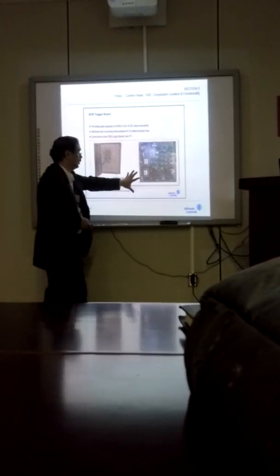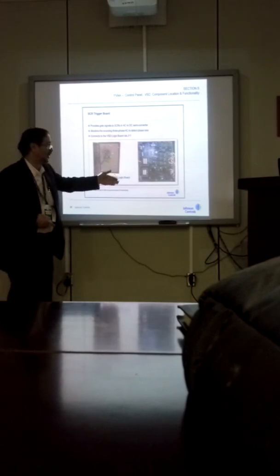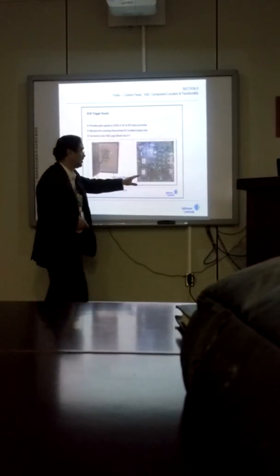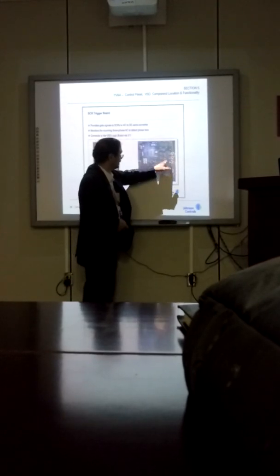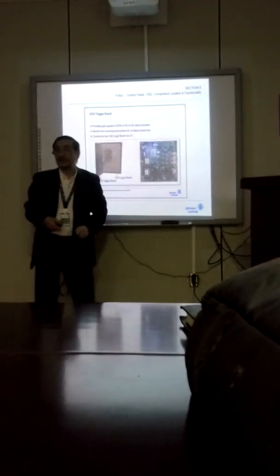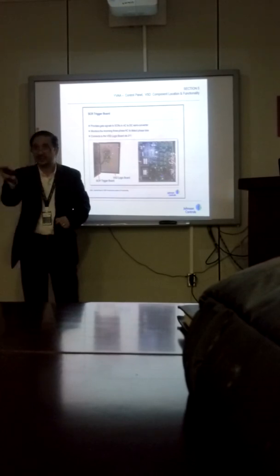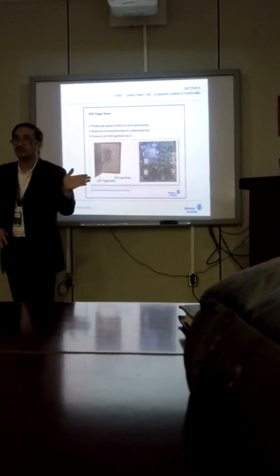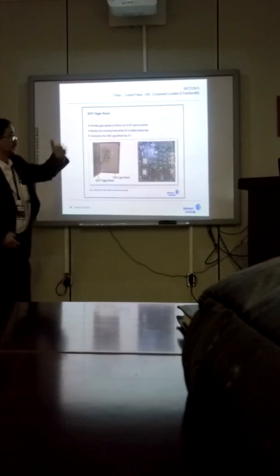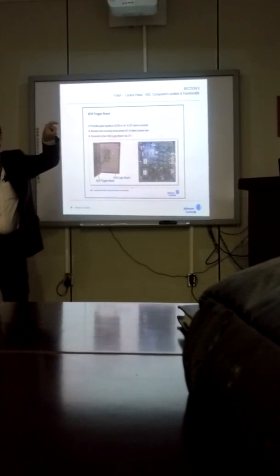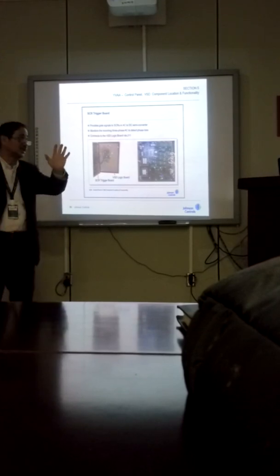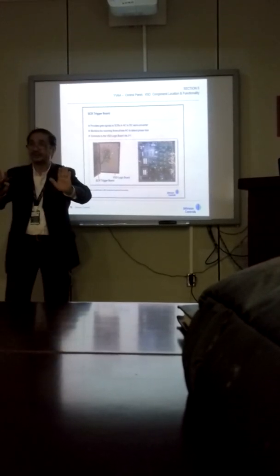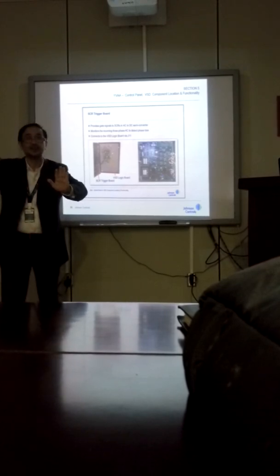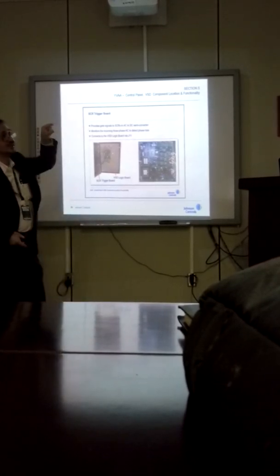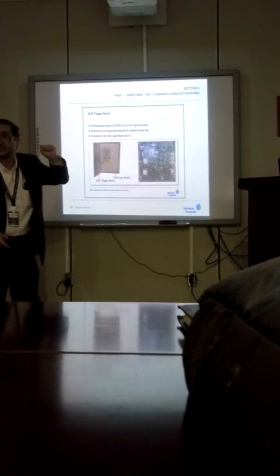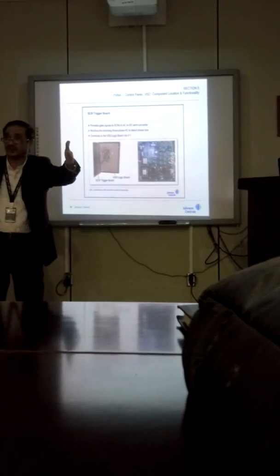Another board, which we call the semiconductor board or the SCR trigger board. It has safety features which provide monitoring of three-phase. If one of the phase line inputs is not there, the machine will shut down. If it is running, it will give you a single phase loss voltage. If the machine is on standby and you would like to start, it will not start. It will give you single phase loss phase voltage. Even for a half cycle of a 60 cycle.